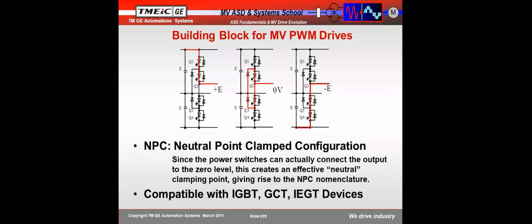Now, this is something that you don't see in low voltage drives. It's called neutral point clamping. And basically, the reason you don't see it in low voltage drives is because you can't afford it. In low voltage drives, you have to minimize the number of diodes, the number of IGBTs in there in order to have a drive that will be cost effective. And so you just don't have the money to do this. But in medium voltage drives, you can actually connect the power switches to a zero level, effectively creating a neutral clamping point for the motor, and that keeps your motor voltages where you want them.